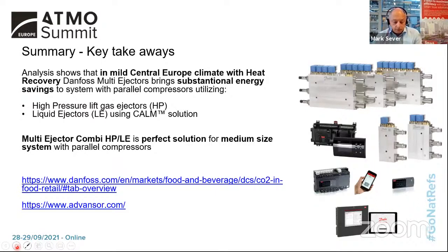And as a kind of conclusion, I would like to say that very often in ejector discussions, we are always talking about warm weather conditions. Here it's a proof of the possibility that you can use ejectors even in the, what we can say, mild Central Europe climate zone. With heat recovery, you will really gain a lot of savings because there are a lot of hours in the year your ejector will bring you benefit.